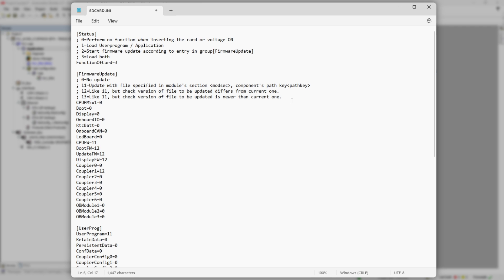On the other hand, parameter Display FW has value 12, and in this case, before updating, PLC will check if version of existing display firmware is different from what we're trying to load. And if it is, then update will be performed. There's also value 13, which means only newer than existing firmware will be updated.